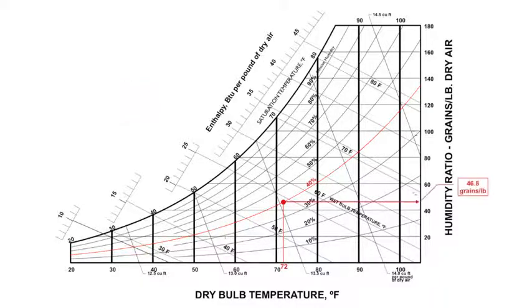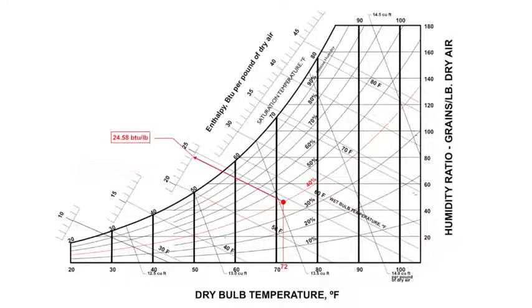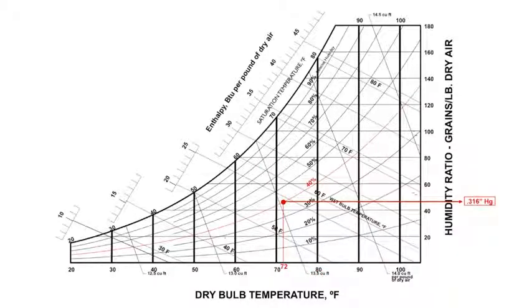If we read to the right we can see that the humidity ratio is 46.6 grains per pound. If we read to the left we can see that the dew point is 46.4 degrees. The enthalpy is 24.58 BTUs per pound. The specific volume is a little over 13.5, and the vapor pressure is 0.316 inches of mercury.